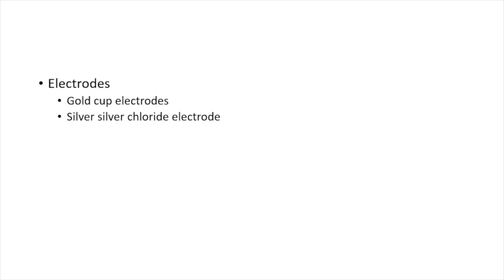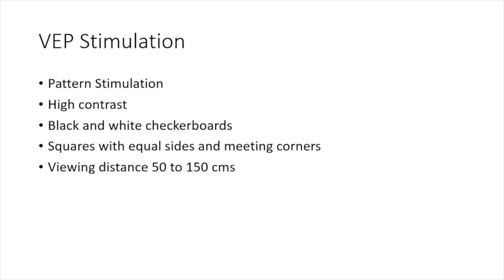Regarding electrodes and stimulation: the pattern stimulation should have high contrast — at least more than 80% contrast difference between the black and white checkerboards, with 100% being better. The squares should have equal sides, meeting corners, and viewing distances of 50 to 150 centimeters. The stimulus difference should occur without change in average luminance, meaning the brightness of the screen should not change when the pattern reverses.